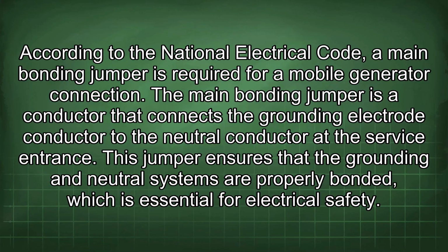According to the National Electrical Code, a main bonding jumper is required for a mobile generator connection. The main bonding jumper is a conductor that connects the grounding electrode conductor to the neutral conductor at the service entrance. This jumper ensures that the grounding and neutral systems are properly bonded, which is essential for electrical safety.